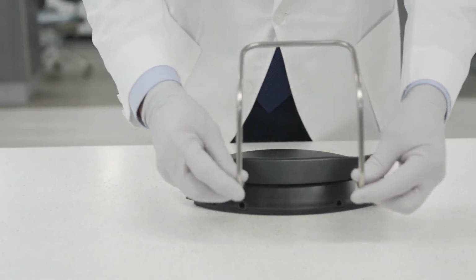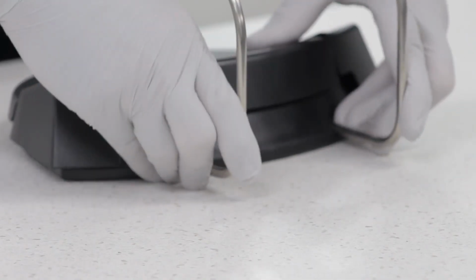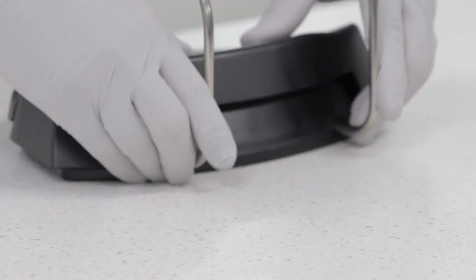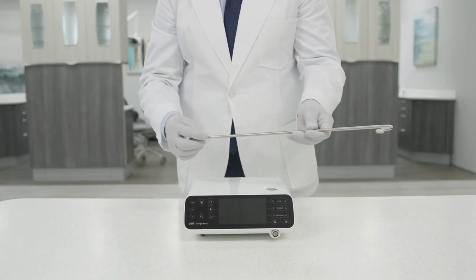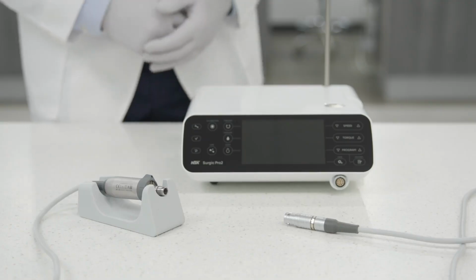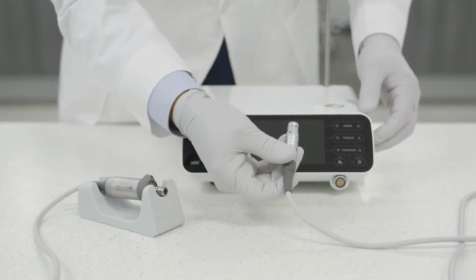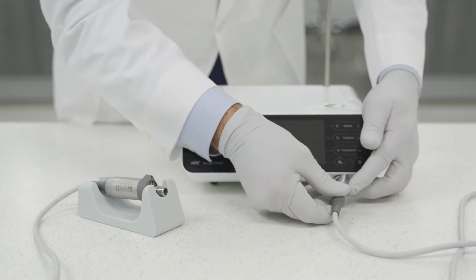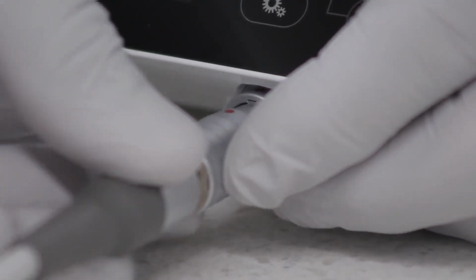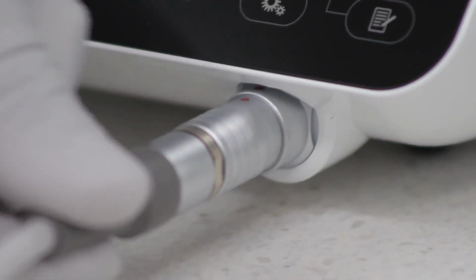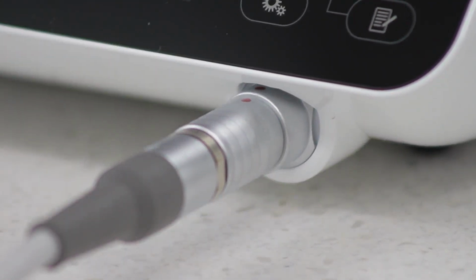Insert the foot control hanger by squeezing it and aligning the guides of the hanger with the holes on the foot control. Next, mount the coolant solution hanger post and hang the saline bag. Connect the motor cord by aligning the marks on the cord connector and the connection on the control unit. Push in the connector until you hear a click. Pull the cord slightly to ensure the connector is locked in place.